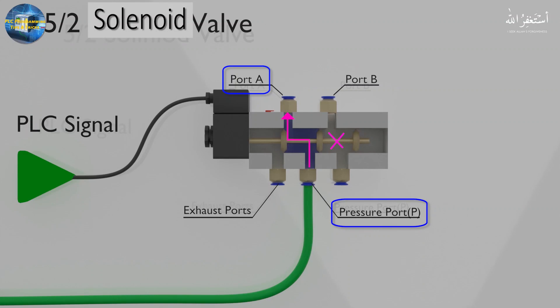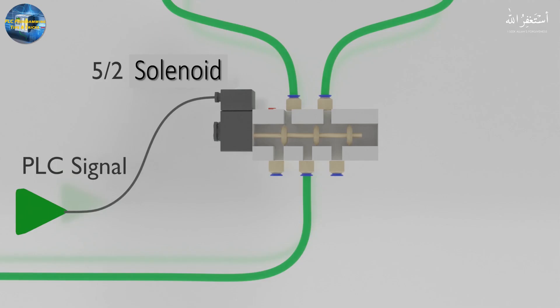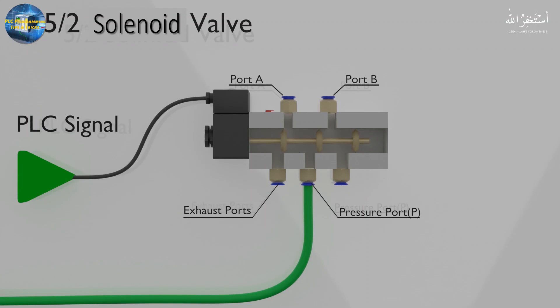When port P is linked to port A, the spool blocks the entry of air towards port B. Similarly, when port P is linked with port B, the spool blocks the entry of air towards port A. The spool moves when the solenoid coil is energized by a signal coming from the PLC. There are also exhaust ports in the solenoid valve, which we will discuss shortly.